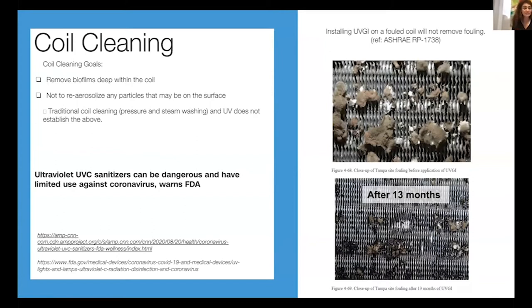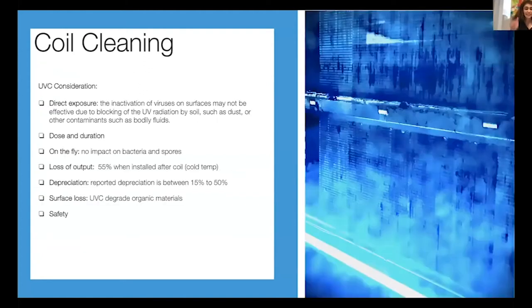that if your coil is fouled, don't put UV and expect that the fouling will go away. If you're considering putting in UV, you need to clean your coil mechanically. You need to make sure your coil is clean first. And this is a picture that my team took. It's on the right-hand side. It's UV light installed in a mechanical room, basically in an air handling unit after the cooling coil, for 7 months. And still you can see clearly stuff is still growing on the coil. So you might ask yourself, why is that? Why is stuff still growing on the coil?